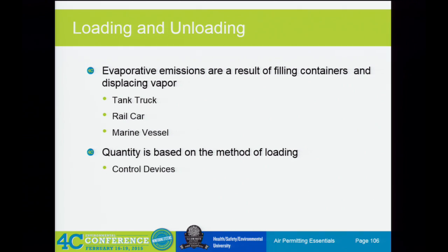Loading is an interesting case. Loading can range anything from a one-bay truck loading facility all the way up to bigger than Panamax vessels out on the ship channel. So loading emissions come from displacing vapor in the vessel. If this one's already loaded, but if it's empty, then it's full of vapor. And as you fill it, those vapors have to go somewhere.